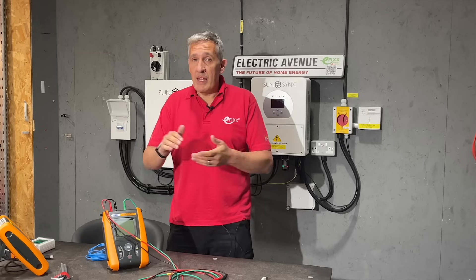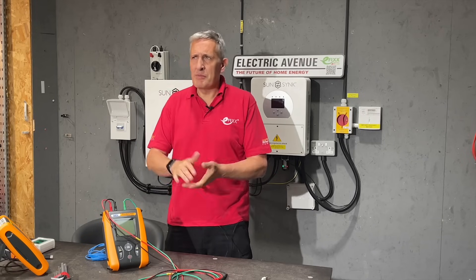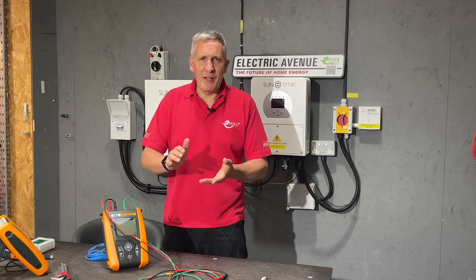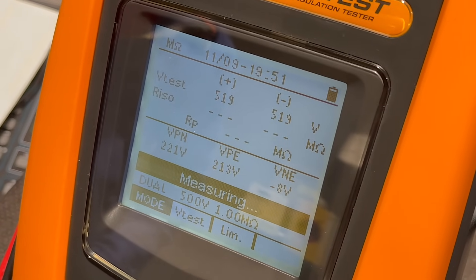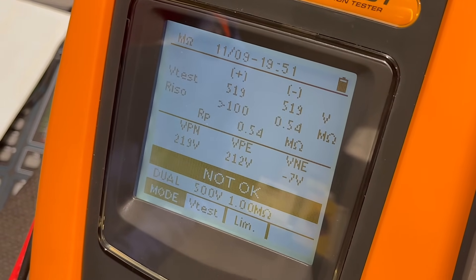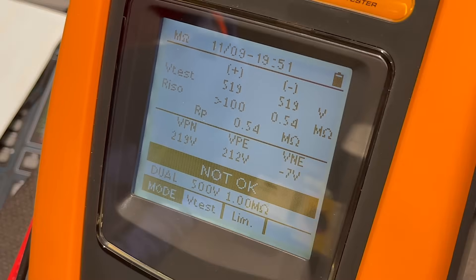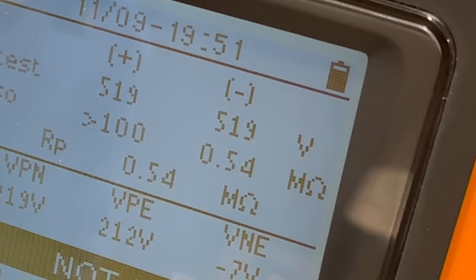This test is performed under live conditions — you don't have to disconnect the panels. What would be the point in that? You wouldn't see the insulation of the panels. The test takes around 20 seconds to complete and the results are in. We can see a great result on the positive line with a resistance greater than 100 megaohms. However, we have a problem on the negative line with a resistance of around half a megaohm, which has resulted in a test fail.